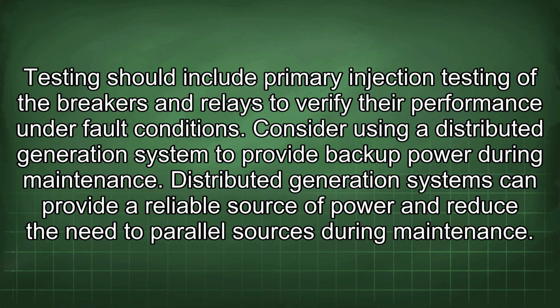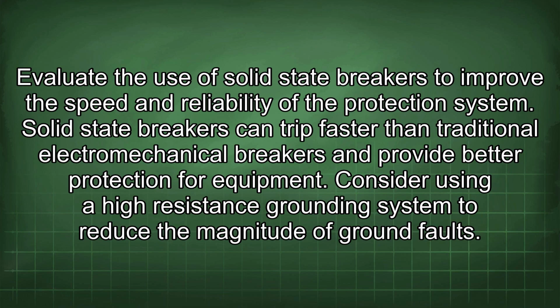Distributed generation systems can provide a reliable source of power and reduce the need to parallel sources during maintenance. Evaluate the use of solid-state breakers to improve the speed and reliability of the protection system. Solid-state breakers can trip faster than traditional electromechanical breakers and provide better protection for equipment.